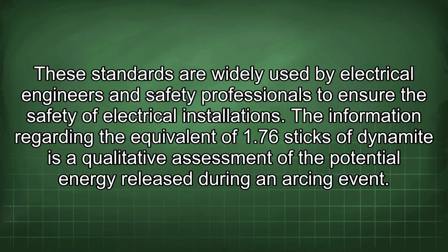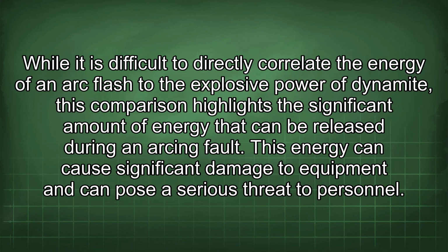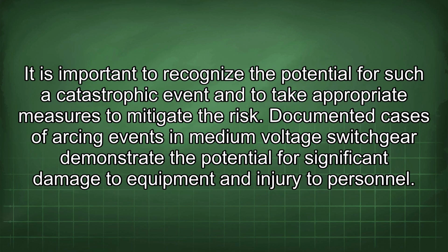The information regarding the equivalent of 1.76 sticks of dynamite is a qualitative assessment of the potential energy released during an arcing event. While it is difficult to directly correlate the energy of an arc flash to the explosive power of dynamite, this comparison highlights the significant amount of energy that can be released during an arcing fault. This energy can cause significant damage to equipment and can pose a serious threat to personnel.